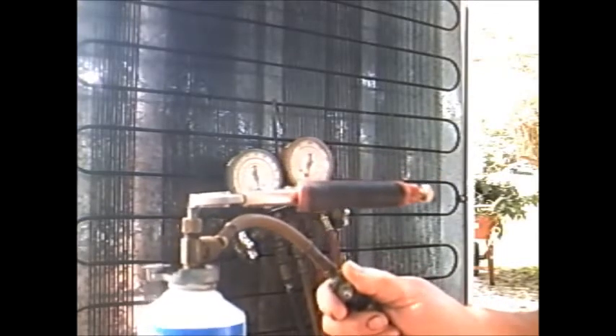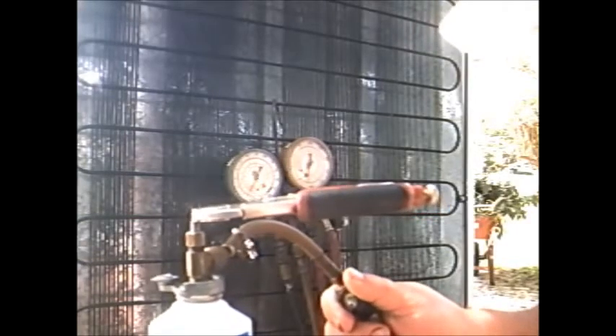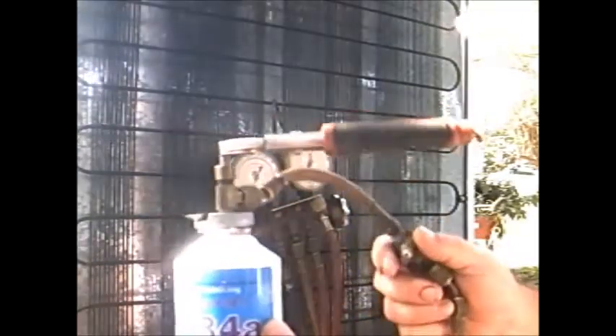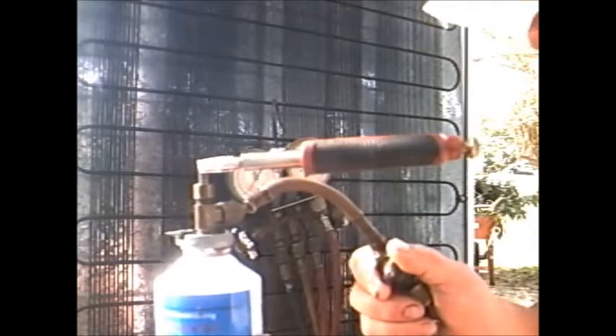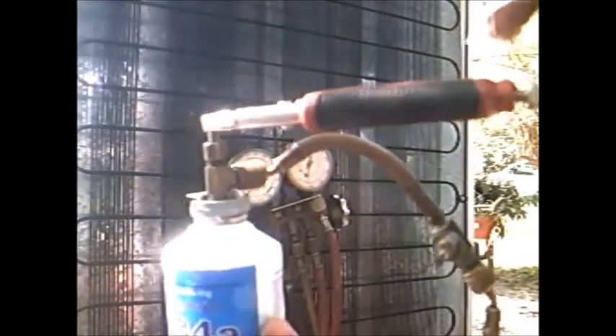See, it's pulling it down into the red zone. We want it out of the red — we want to get it to between zero and five PSI when we get through. We don't want to exceed five pounds while charging. We don't want it to go above 10, for fear that we'll wreak havoc on the little reed valves in there. We don't want to force it in too fast, we don't want liquid going in — we want to let it go in nice and slow.